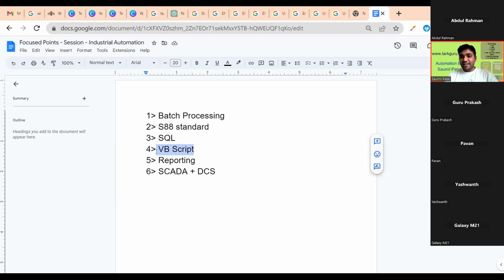To dump the data in SQL, you need to make the connection between your SCADA and the SQL - that connectivity is very much important. After connecting SCADA and SQL database, you need to dump your data points to the SQL database, and for that VB scripting is required, because you need to write down the script. There is no ladder logic, no function block diagram, no chart programming here, because you are dealing with the SQL database. So scripting is mandatory.